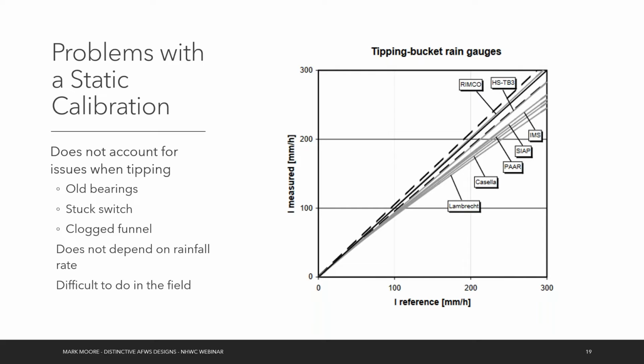And then the last thing about static calibrations is that they're incredibly difficult to do in a field. Oftentimes tipping buckets are up in the air, 10, 15 feet up. You're on a ladder, it's a windy day, the bucket's shaking, a big truck drives past, and it tips sooner than you're expecting it to. So this is something that's usually reserved for the bench, not done in the field.